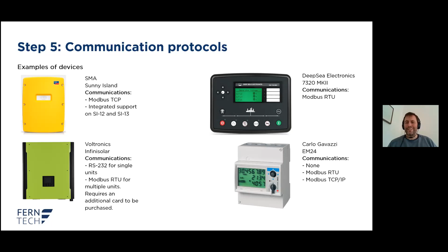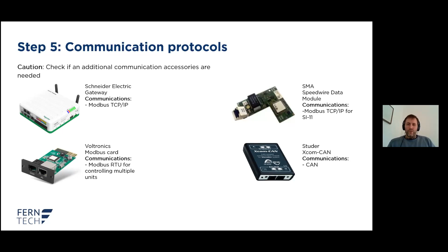The same applies with accessories - sometimes you need a communication gateway to make a controller communicate with a device. These are just some examples: sometimes you need an Ethernet switch, sometimes, as Pablo mentioned before, an Xcom-CAN to convert the CAN signal to the internal proprietary communication bus from Studer. That's also very important to take into account.